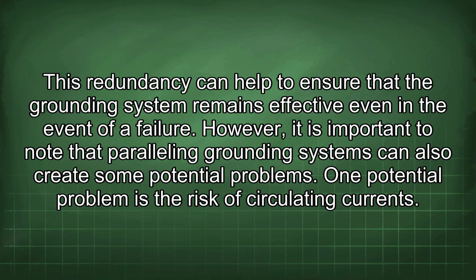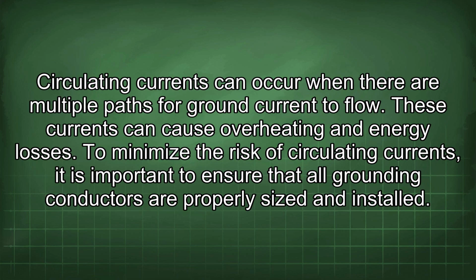However, it is important to note that parallel grounding systems can also create some potential problems. One potential problem is the risk of circulating currents. Circulating currents can occur when there are multiple paths for ground current to flow. These currents can cause overheating and energy losses.